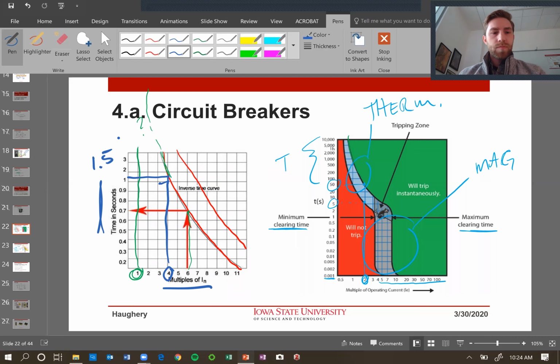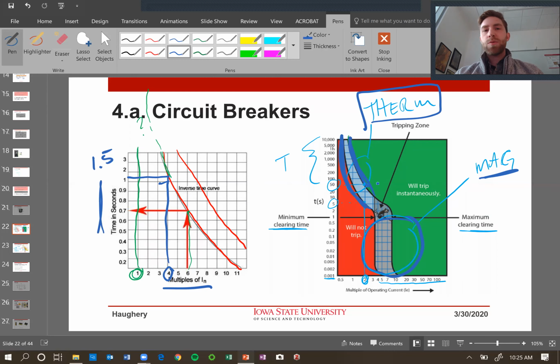Specifically looking at more of a trip curve that you would see for an actual circuit breaker. This on the left is very generic. On the right is more traditional, what you would see if you pull up the trip curves for that circuit breaker. You're going to have a couple different regions. You're going to have a magnetic trip region, so anything in this part of the curve is almost instantaneous. It's going to trip very quickly. The thermal trip section, right? That's anything on this more gradual slope. That's where ideally you want to design or select that circuit breaker to trip. And anything in this middle point is the in-between.